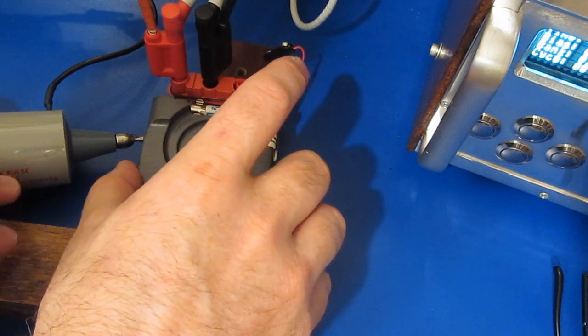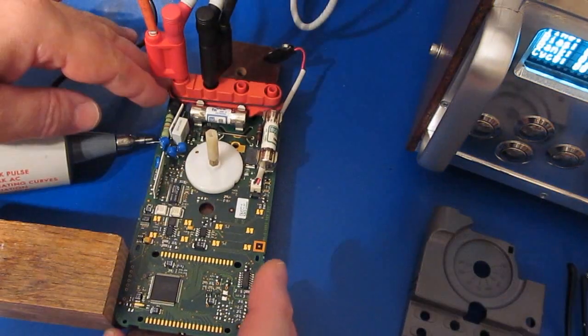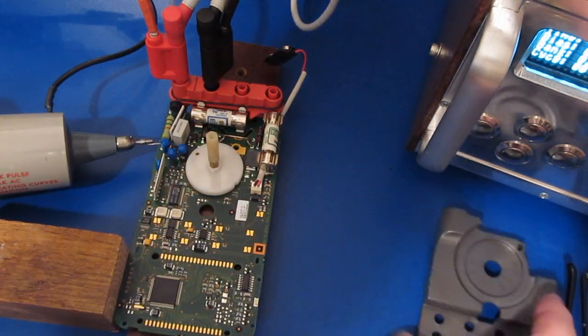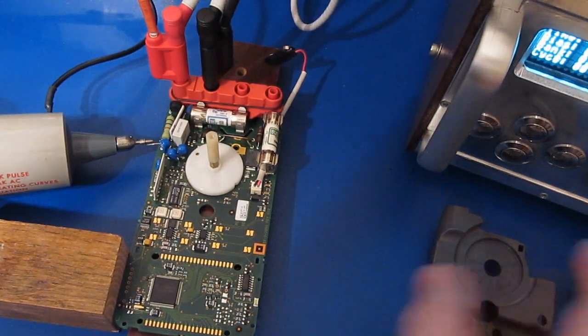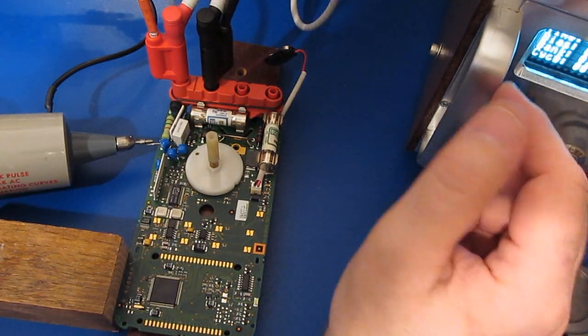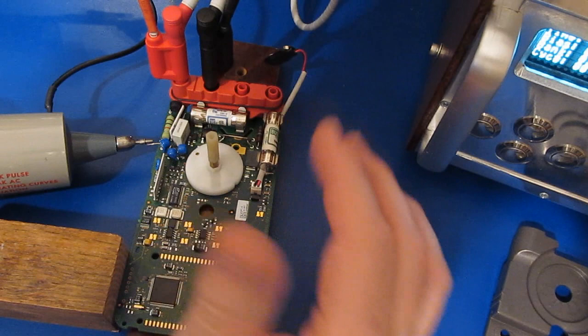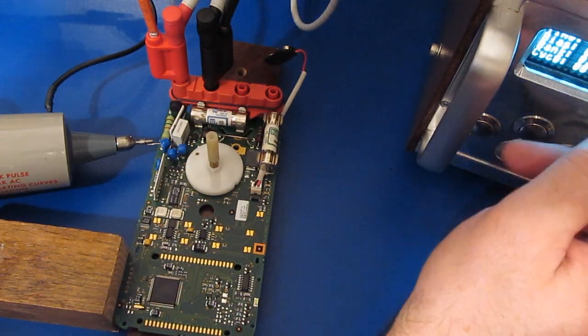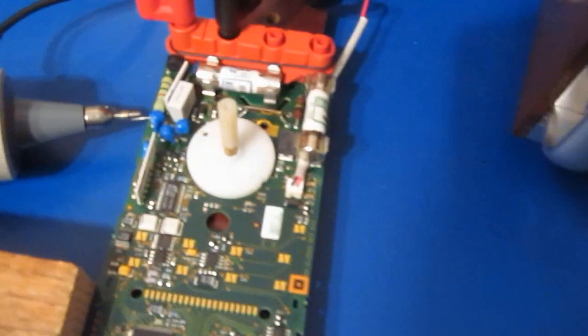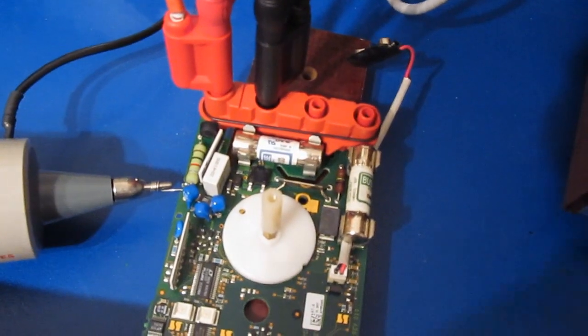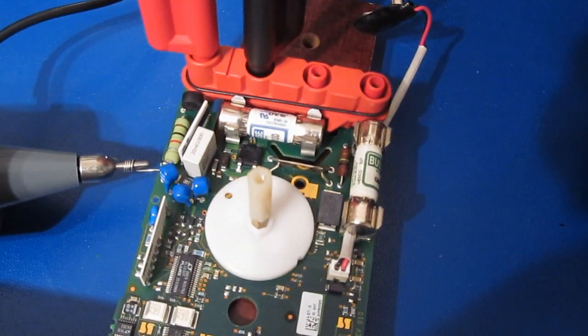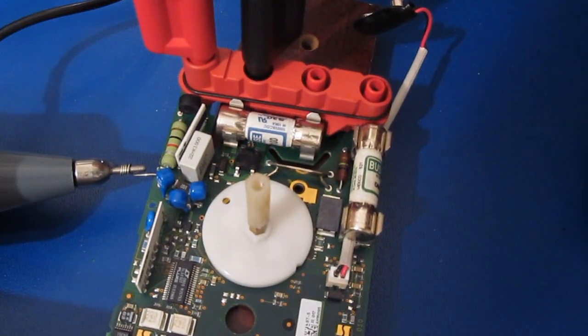So it's currently set for the resistance mode, and the clamp will actually be engaged now. I'm going to apply 5 transients, both positive and negative this time, keeping this at 4,000 volts. Just going to move the camera in a little closer. If something does break down, we should be able to see it.